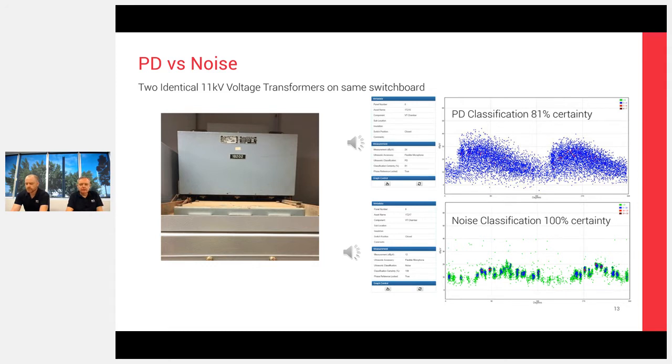You can see the top one there, we've got a phase resolved plot which is locked to the sine wave, but is sort of stochastic, sort of random around the same spots. We've got two significant clusters 180 degrees apart from each other, and there's sort of a random nature.